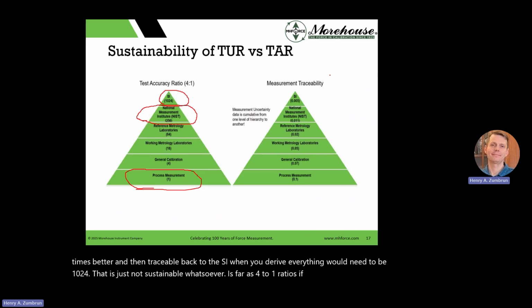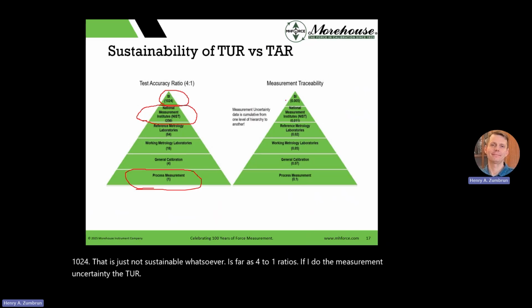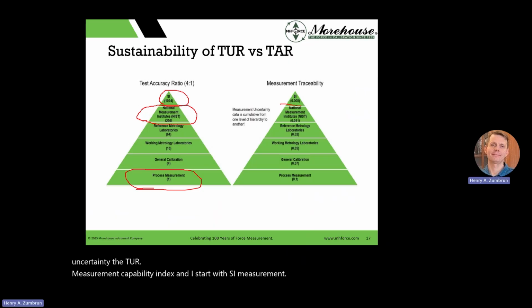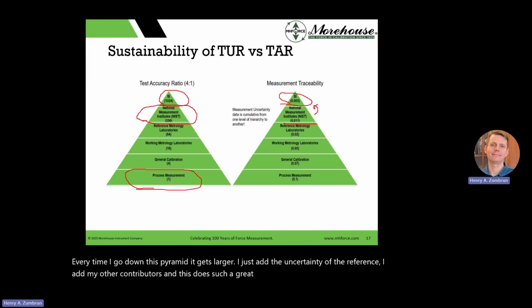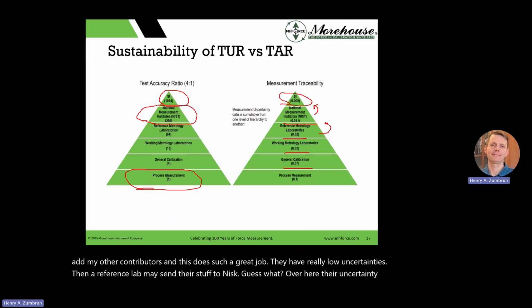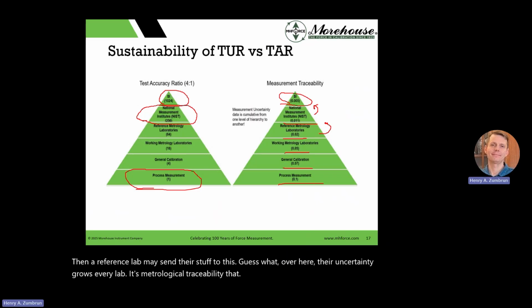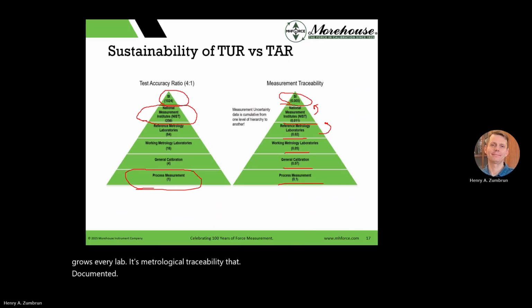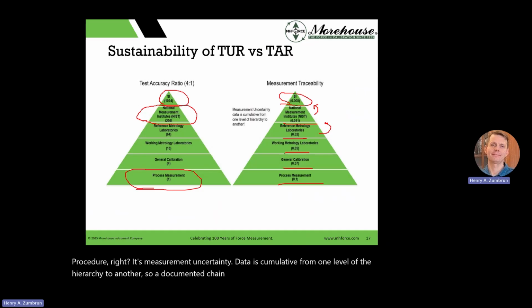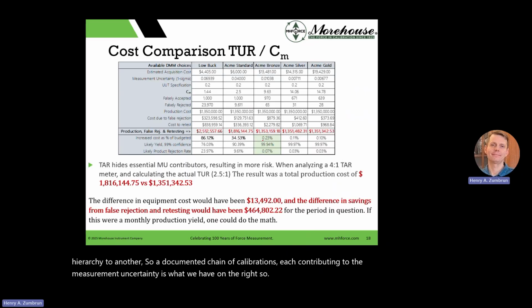If I do the measurement uncertainty, the TUR measurement capability index, and I start with the SI measurement at 0.05, every time I go down this pyramid, it gets larger. I just add the uncertainty of the reference, and I add my other contributors. NIST does such a great job. They have really low uncertainties. Then a reference lab may send their stuff to NIST, and guess what? Over here, their uncertainty grows. Every lab, it's metrological traceability: a documented procedure, right? Measurement uncertainty is cumulative from one level of the hierarchy to another. So a documented chain of calibrations, each contributing to the measurement uncertainty, is what we have on the right, which is the definition of metrological traceability.